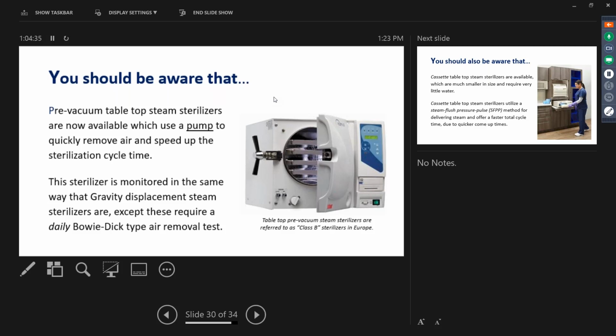So we've got to make sure that if they move from gravity to pre-vacuum, that they're not just doing this and paying no attention to their instrument IFUs or their packaging IFUs. Maybe they're using a pouch only sold for dental, and so they know it's gravity, so they don't have gravity stated on their pouch. You have to make sure all this is compatible.